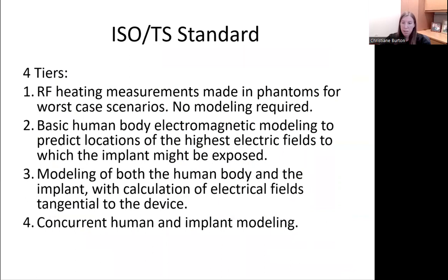Lastly, I'll briefly explain the ISO TS standard. In brief, the 4 tiers are as follows. 1. RF heating measurements made in phantoms for worst-case scenarios where no modeling is required. 2. Basic human body electromagnetic modeling to predict locations of the highest electric field to which the implant might be exposed. In general, Tier 1 and 2 assessments are usually done for small, compact devices such as cochlear implants, pressure sensors, implanted monitors, and leadless pacemakers.